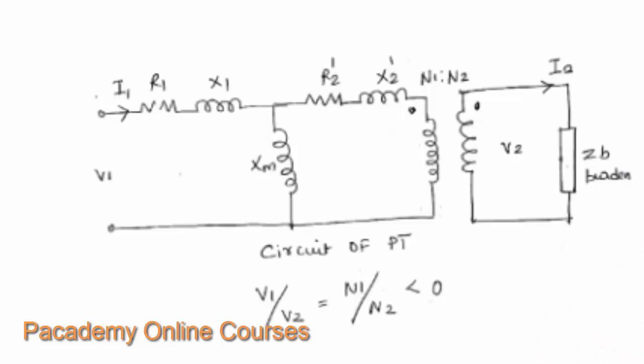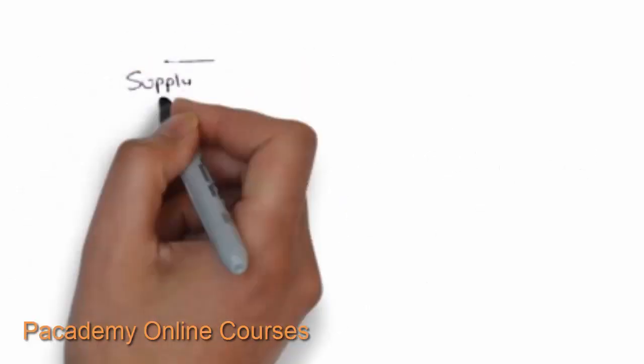For this transformer, V1 by V2 is always greater than 1, N1 by N2 is greater than 1, while N2 by N1 is less than 1. R1 and X1 are the primary winding resistance and reactance, and R2 and X2 are the secondary winding resistance and reactance transferred to the primary side. N1 by N2 is the transformation ratio and XM is the magnetizing current equivalent. The burden is the equipment connected, which is typically the voltmeter.